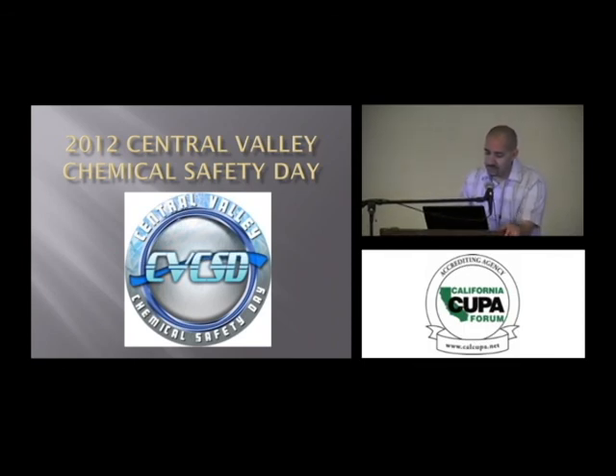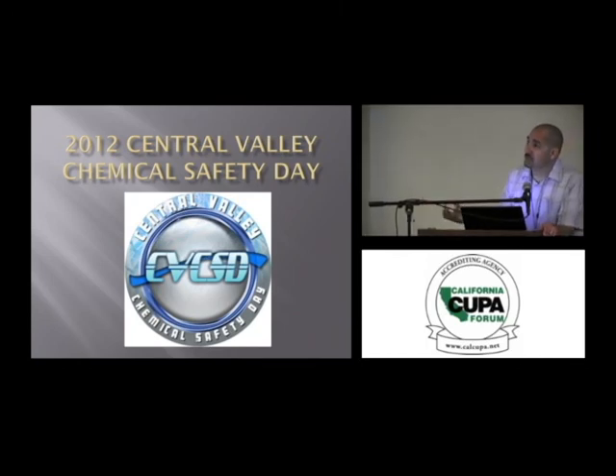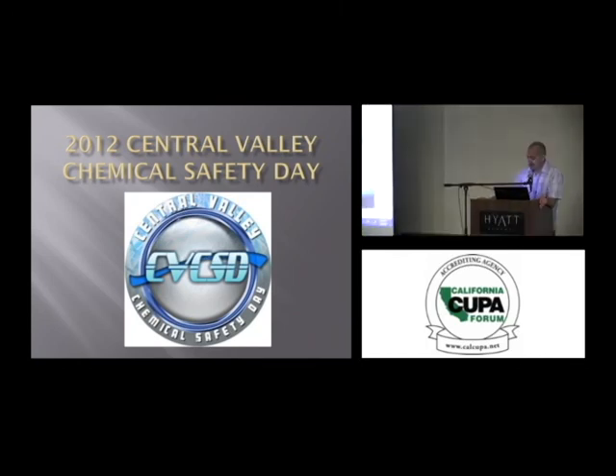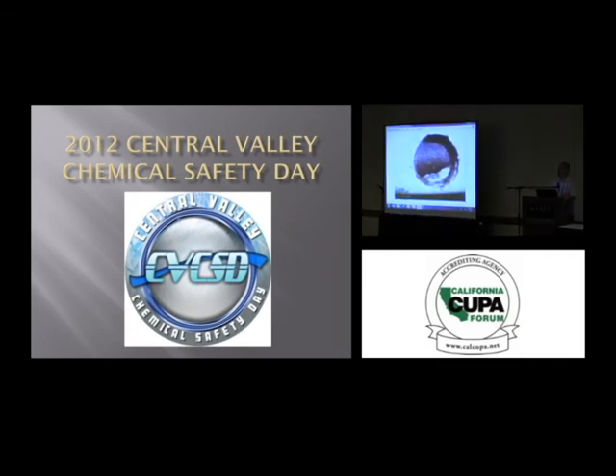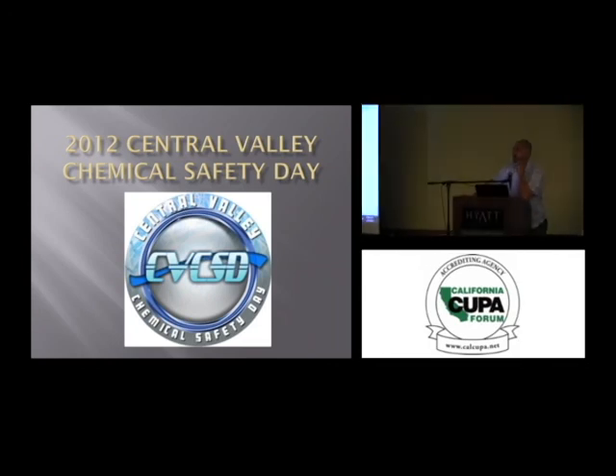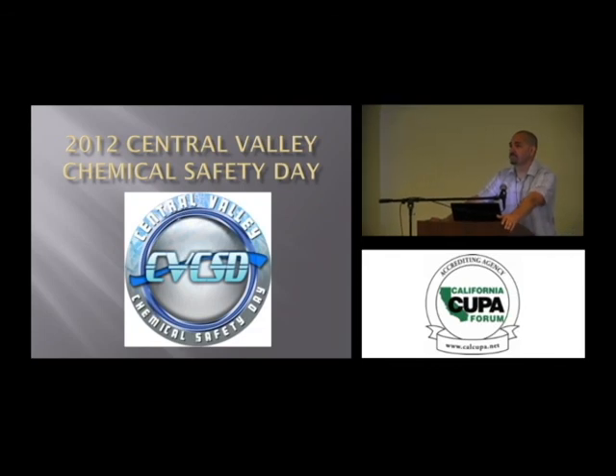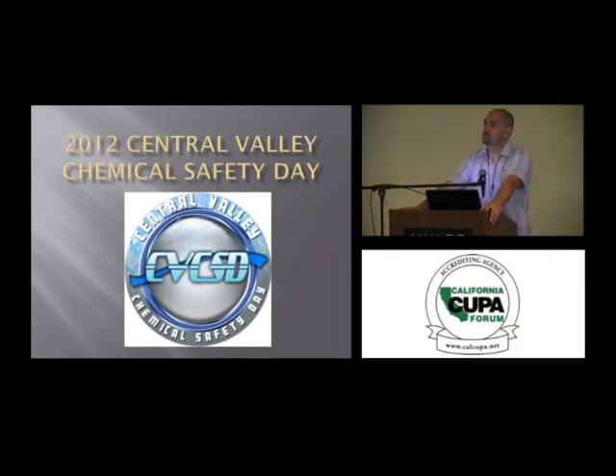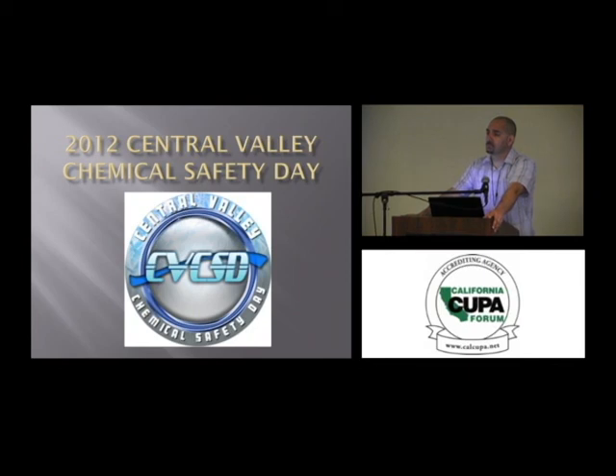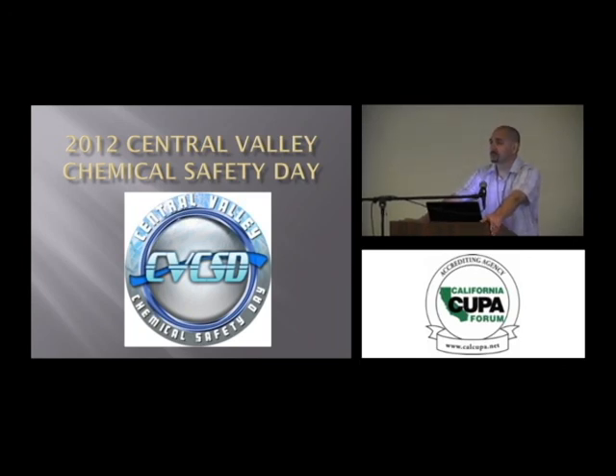One thing, if you see the corrosion outside, there you go. If you've got corrosion outside of the insulation, you know it's bad on the inside. We typically will use a hole saw and a cordless drill, 2 inches, 3 inches, and we'll take out a plug at the suspect areas. If we see corrosion, then we start removing insulation, 3-4 feet at a time. Leave it open so the owner-operator can see it. And we'll do that again on pipes that change temperature, etc. If the insulation's saturated and it's wet, it's dripping, you probably have corrosion. If you see rust, you probably have corrosion on the outside from it staining.